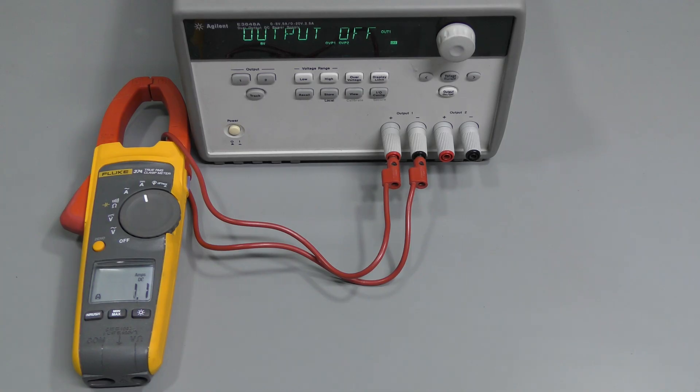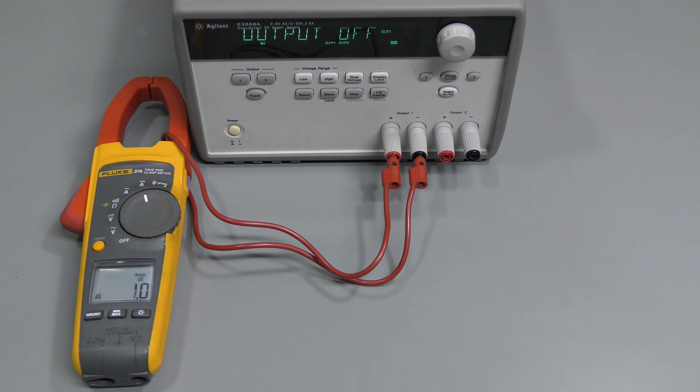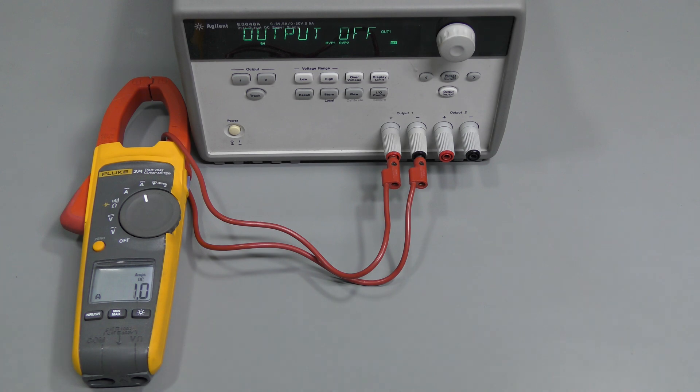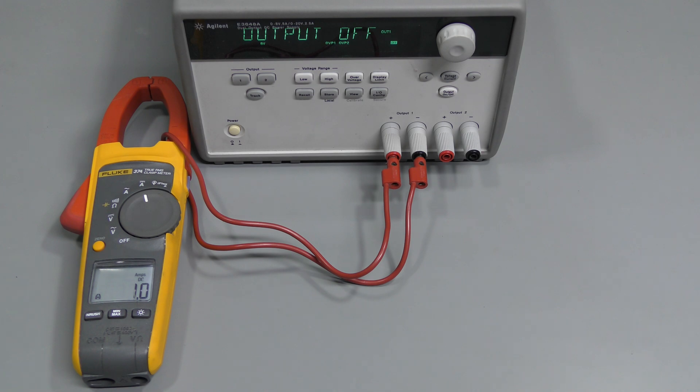And now to the main function of this clamp meter, which is, to state the obvious, current measurement using the clamp. And again, I don't have an AC calibrator, so let's limit ourselves to DC amps, and not all clamp meters can measure that, and I wanted to have a clamp meter with DC amps. This model can measure up to 600 amps, with resolution of 0.1 amp and accuracy of 2%.